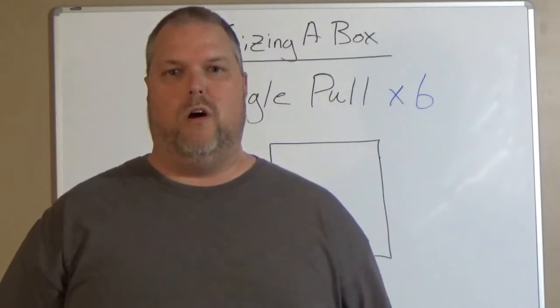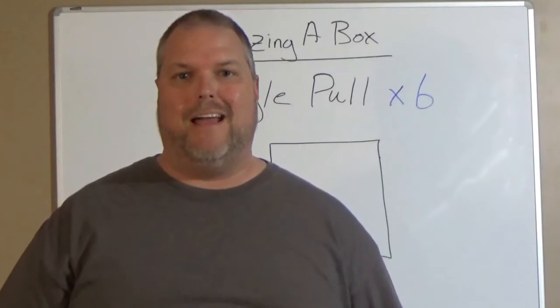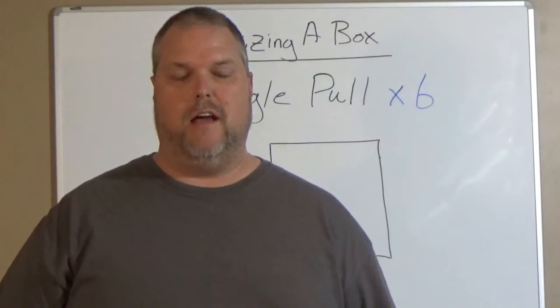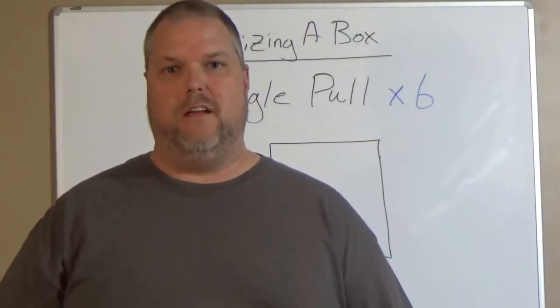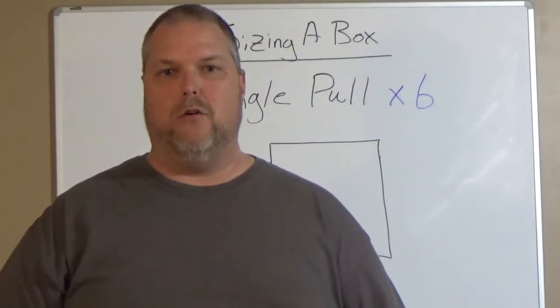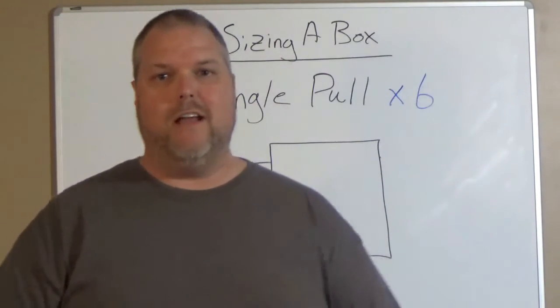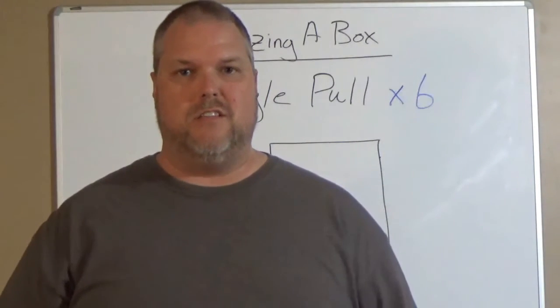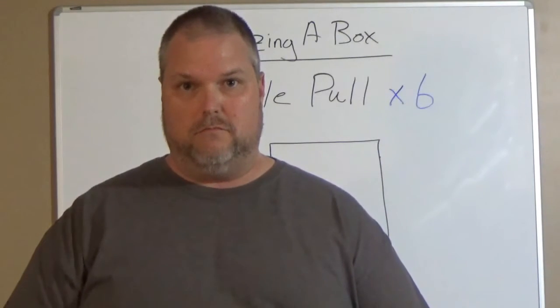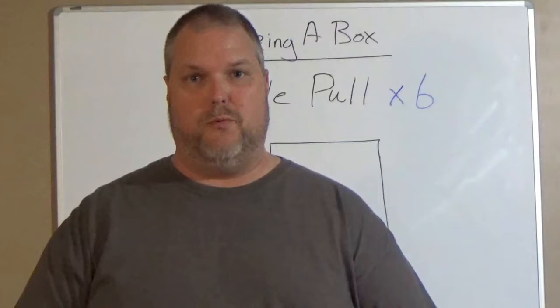At the same time, we don't want to run a 1-inch conduit and put an 18x18 junction box in, because now we're just wasting money. There's a few hundred dollar mistake there. This is why it's very important to understand that when you're doing an angle pull or replacing a 90, because remember, when you're running conduit, 360 degrees is the maximum run of a conduit with bends.